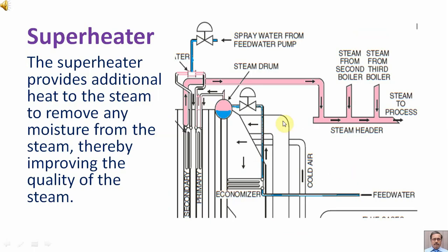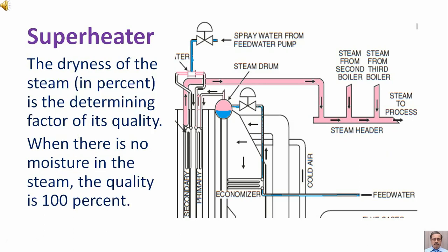The superheater provides additional heat to the steam to remove any moisture from the steam, thereby improving the quality of the steam. The steam leaves the boiler drum, passes through the primary superheater, then through the desuperheater, and then again through the secondary superheater. Finally, the steam goes to the steam header. The dryness of the steam in percent is the determining factor of its quality; when there is no moisture in the steam, the quality is 100%.